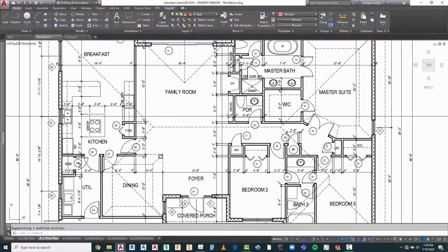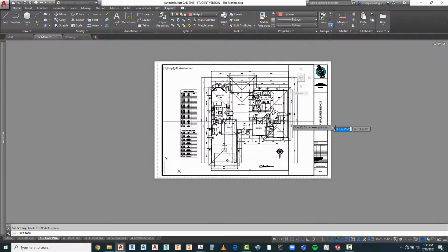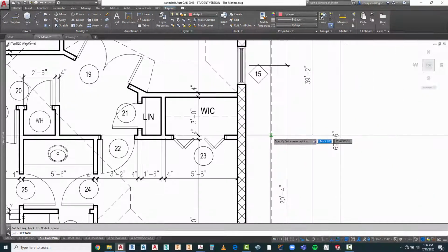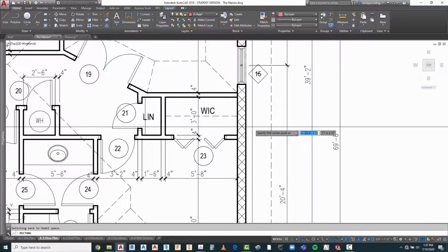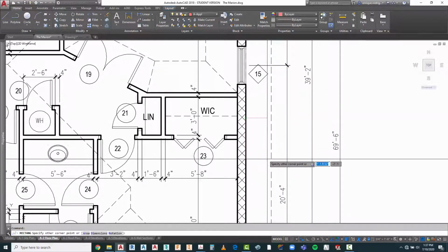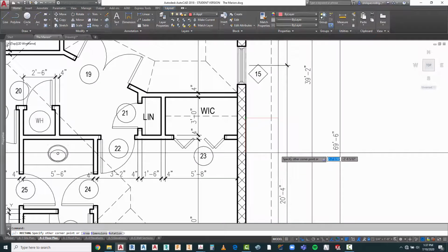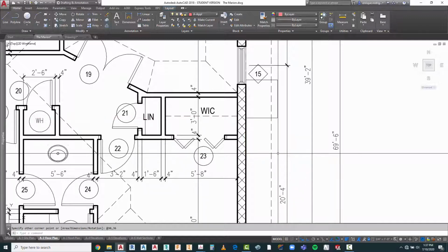So let's go ahead and go to our floor plan. And if we put our air conditioning unit here, we're going to want to put it on a concrete pad. So I'm going to go ahead and size. I'm still in A appliance. I am inside model space. So I'm going to place one here, not too close to this window so the noise isn't too much. I'm going to start here right on the wall, and I'm going to assume that our AC unit, at least our condenser, is going to be 30 by 36. Let's draw that right there.